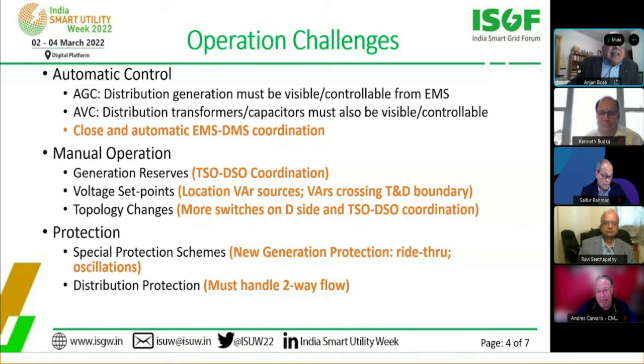So again, the EMS-DMS coordination becomes very, very important. And remember, this is automatic control, nobody's touching anything. So this EMS and DMS coordination has to be done at 4-second intervals, automatically. Look at what happens to manual operation. If you're going to keep generation reserves, let's say for AGC, you may not have enough reserves on the transmission side anymore as time goes on.